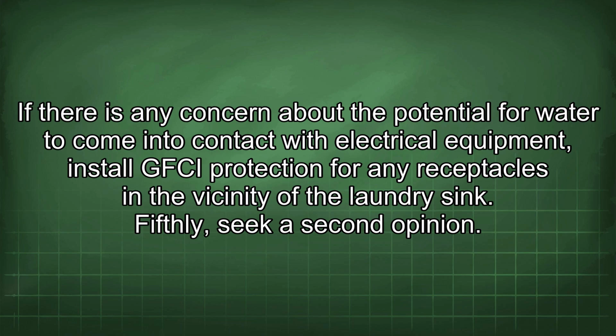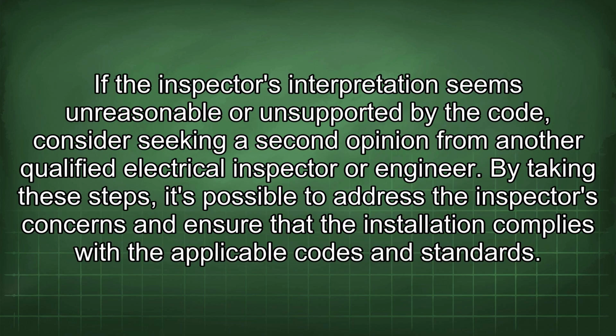If there is any concern about the potential for water to come into contact with the electrical equipment, install GFCI protection for any receptacles in the vicinity of the laundry sink. Fifthly, seek a second opinion.